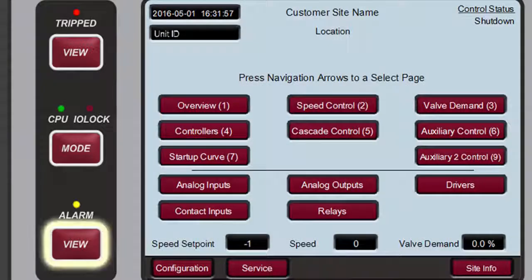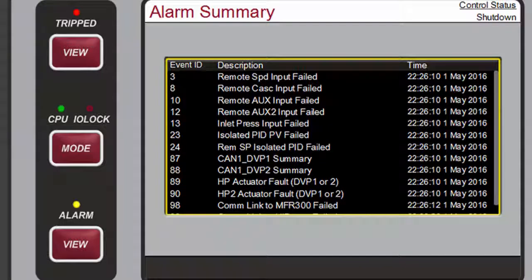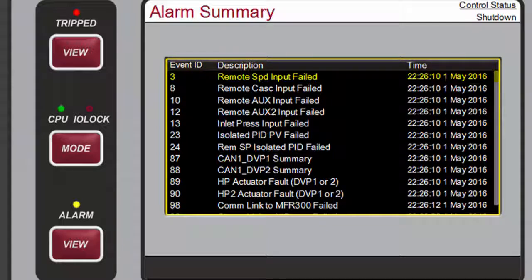Pressing Alarm View opens the Alarm Summary screen. When an alarm is detected, it gets latched in the Event logic. The Alarm Relay is energized, and the Alarm LED illuminates yellow. The cause of the event will be indicated with an Event ID, Description, and Time and Date stamp. The list will always place the first alarm condition to occur at the top of the list. The most recent alarm condition to occur will always be placed at the bottom of the list.